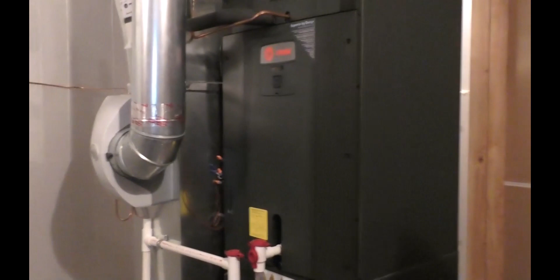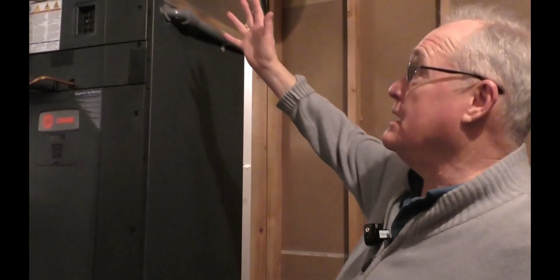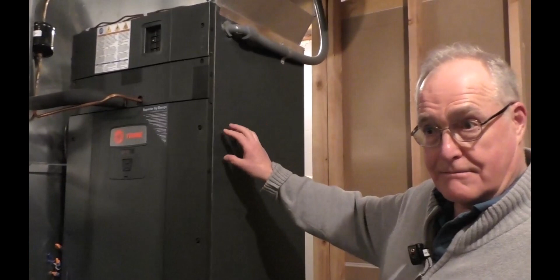Here is our new heater. We use the existing ducting, too late to change it. In here we have the interior heat exchanger for the heat pump, which is outside, and up here somewhere are two heaters like toasters, just convection heaters, like you'd find in a normal electric heating system where they don't have access to natural gas. So when the heat pump can no longer generate enough heat to heat the house, the electric convection coils kick in.